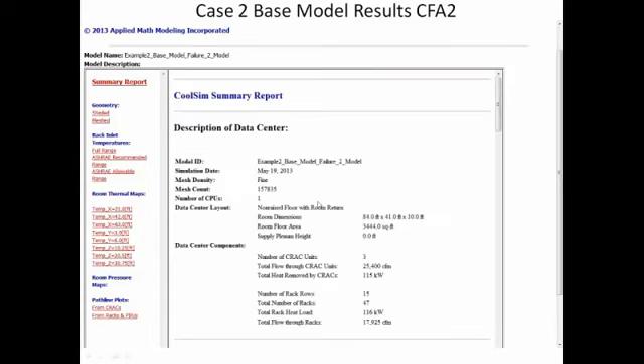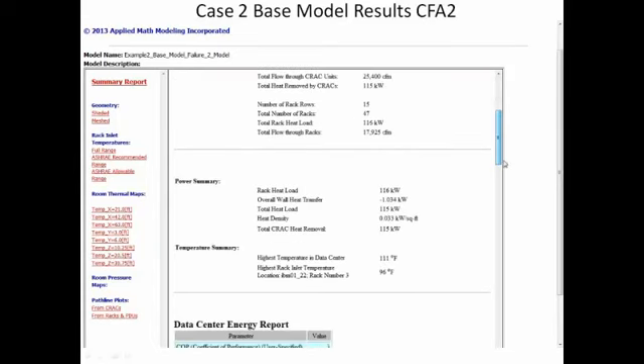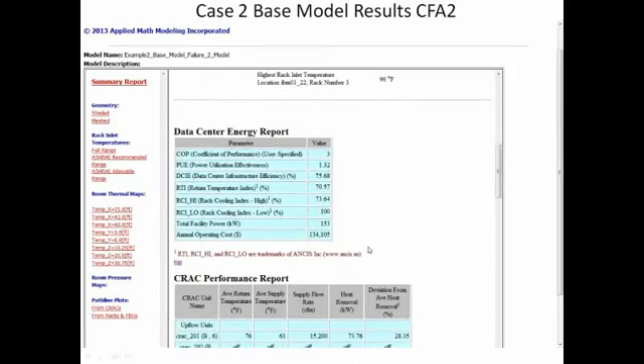So again, if we take a look at this report, it's likely going to be telling us that we've got problems. And yes, you see here my RTI dropped down because I pulled out that 30-ton unit that shut off. RCI high dropped to 73%. RCI low 100%. So I'm not too cold anymore, but I've got problems with hot.